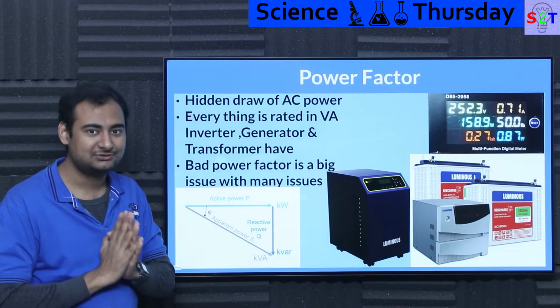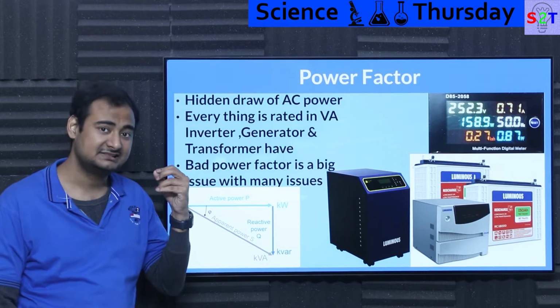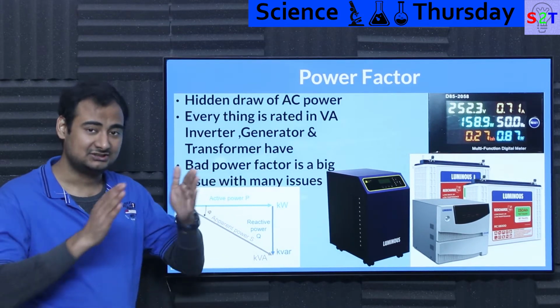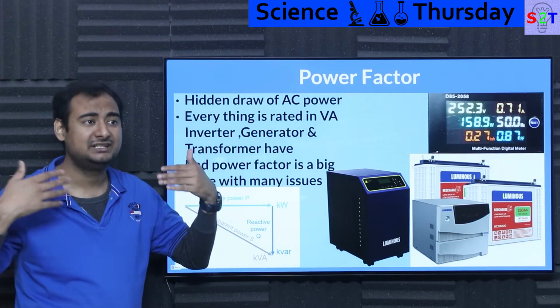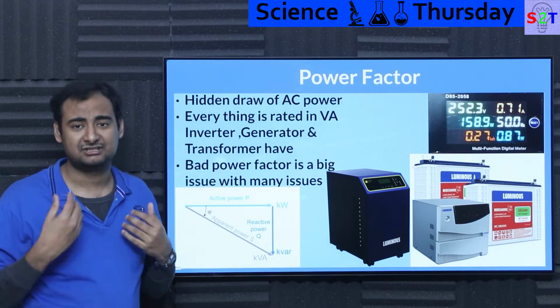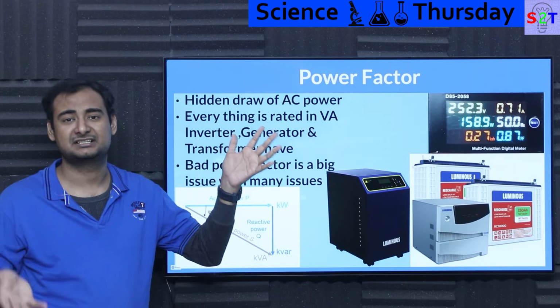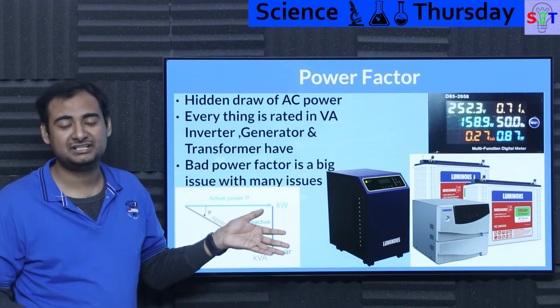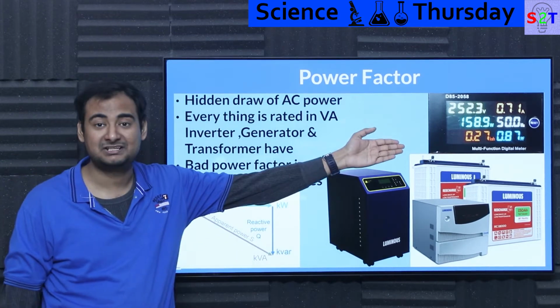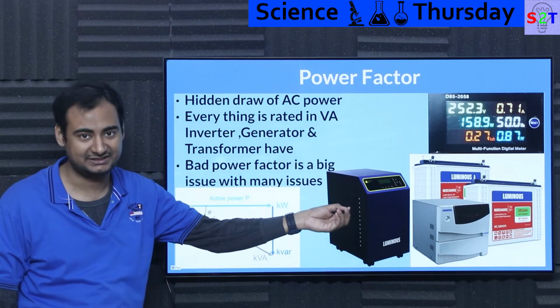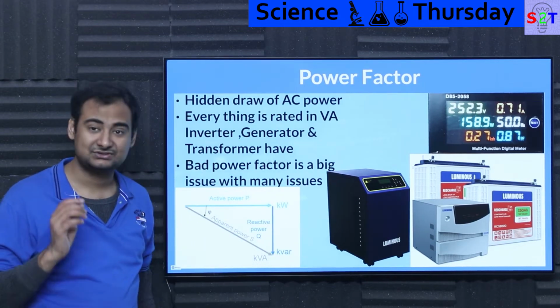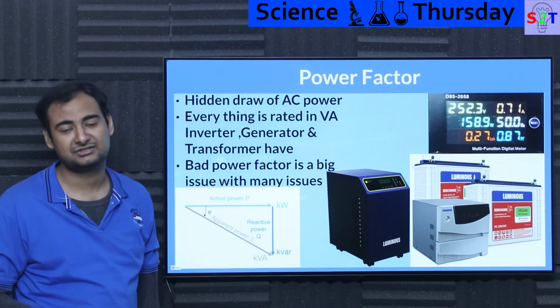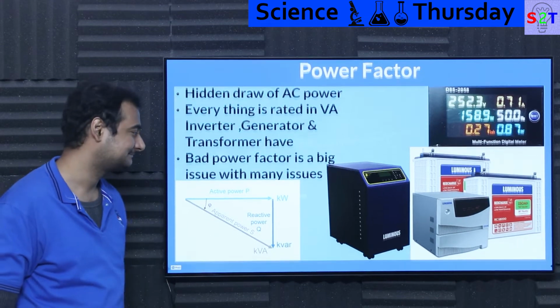So you get the point - you really don't want a bad power factor. This is a hidden thing we don't normally care about, but it adds up over time. Imagine how many small pieces of equipment you have with dirty power factor, and you add them up across a large building - that whole building ends up with dirty power factor, because people aren't paying attention and don't have equipment to measure it. That's why power factor is a hidden enemy, and we must pay attention to it for the sake of everything.